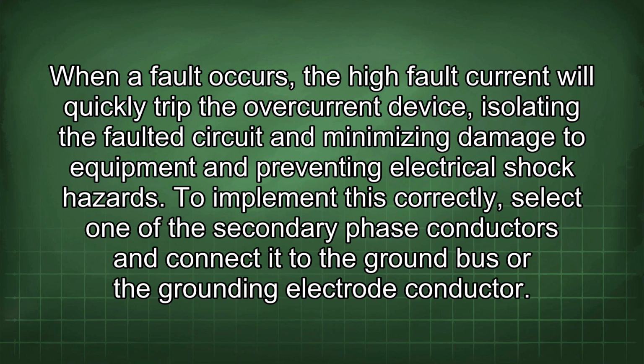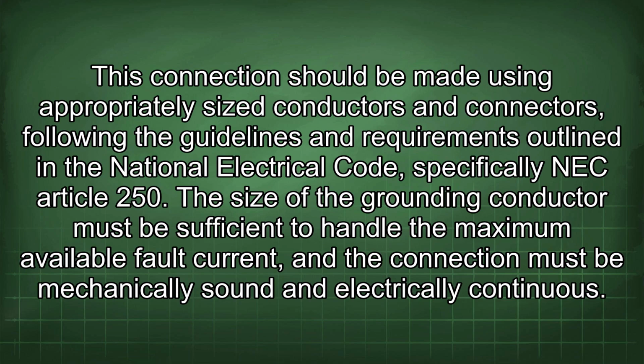To implement this correctly, select one of the secondary phase conductors and connect it to the ground bus or the grounding electrode conductor. This connection should be made using appropriately sized conductors and connectors, following the guidelines and requirements outlined in the National Electrical Code, specifically NEC Article 250. The size of the grounding conductor must be sufficient to handle the maximum available fault current, and the connection must be mechanically sound and electrically continuous.